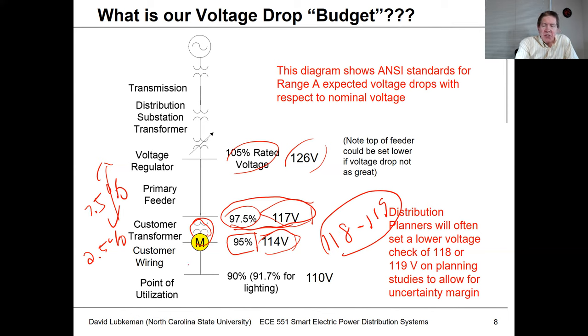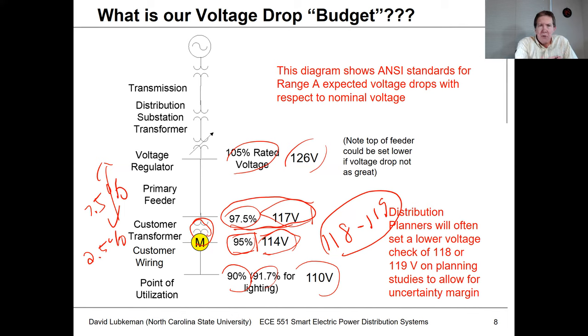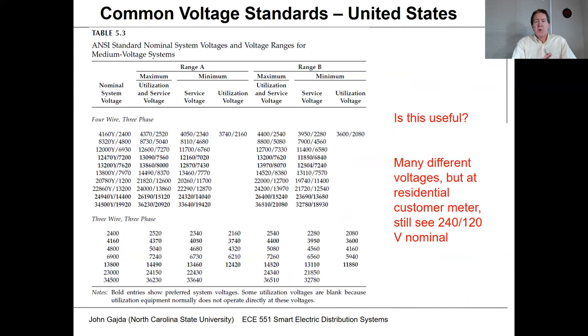Customer wiring is not the utility's responsibility. The customer must ensure that if they take service at 95%, the voltage doesn't drop below 90%, which corresponds to 110 volts. For lighting, it's supposed to be a bit higher than that, since incandescent lighting was sensitive to voltage magnitude.